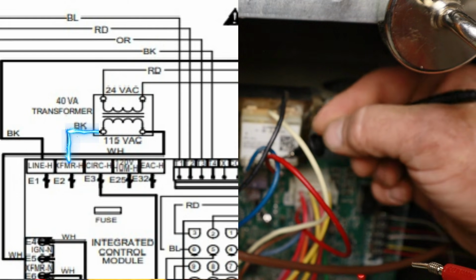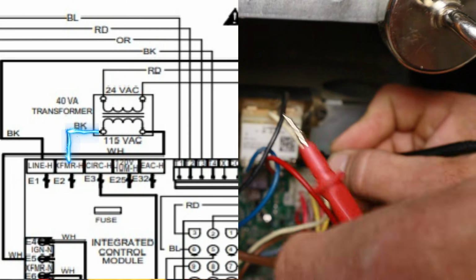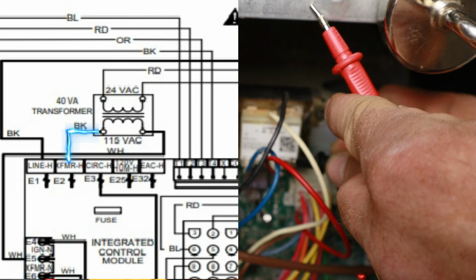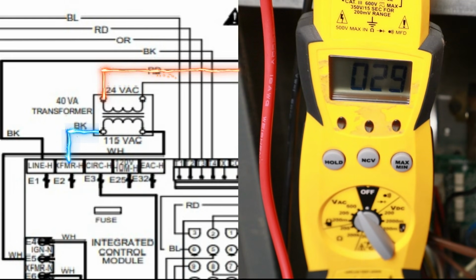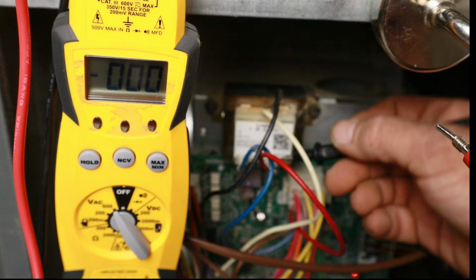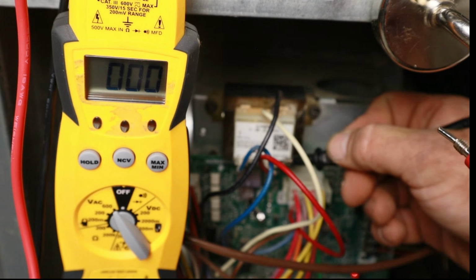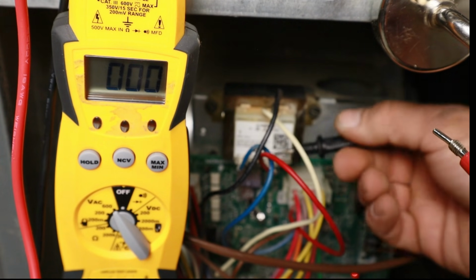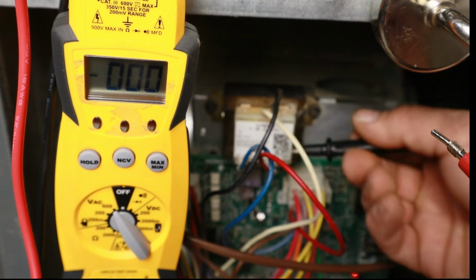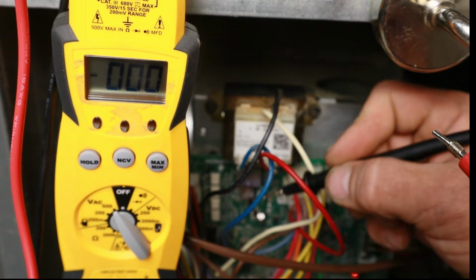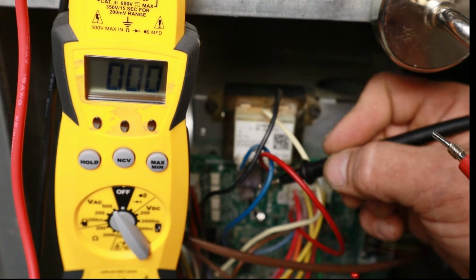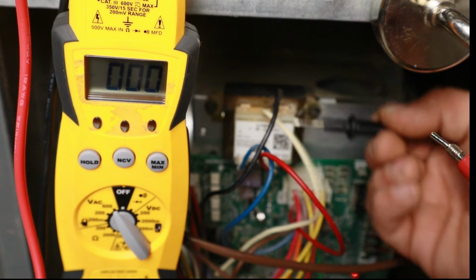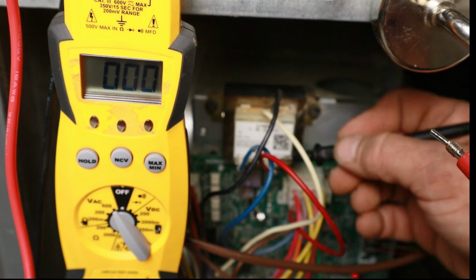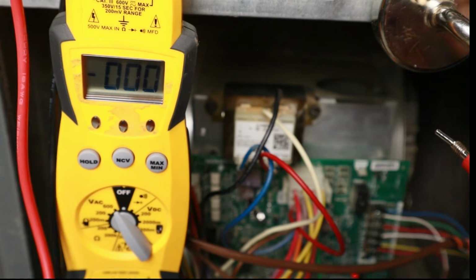So you could see on our schematic we have a red and a blue wire coming off that transformer. It'll be the red wire. I will put my probe on R. I will go to ground or the chassis of the furnace, and you can see I'm reading 29 volts on my multimeter. So that is telling me the transformer is in good shape, it's doing what it's supposed to do. Now if I was not reading 24 or 29 volts off of the secondary side here, that could indicate I have a bad transformer, because even though I have 124 volts on that transformer terminal coming off the control module and going into my transformer, I'm not getting the voltage coming out, and that's a bad transformer.